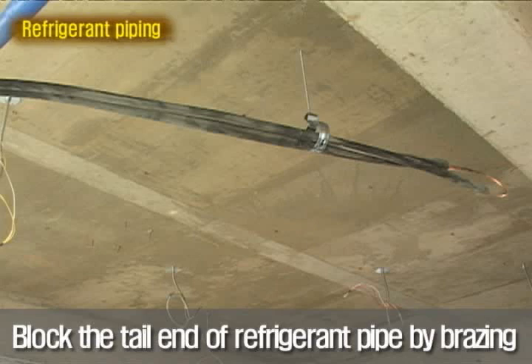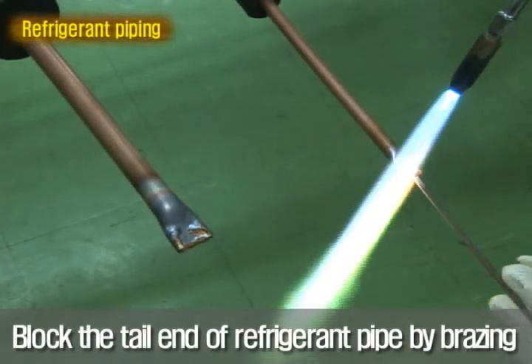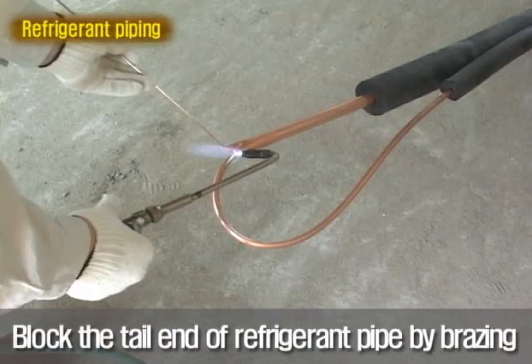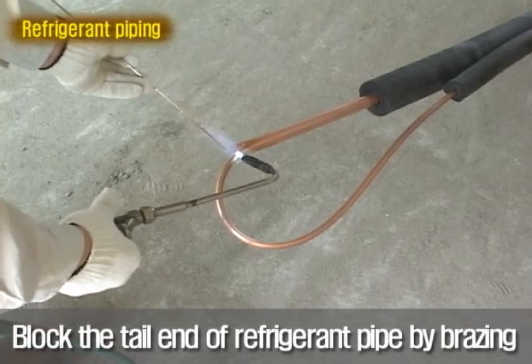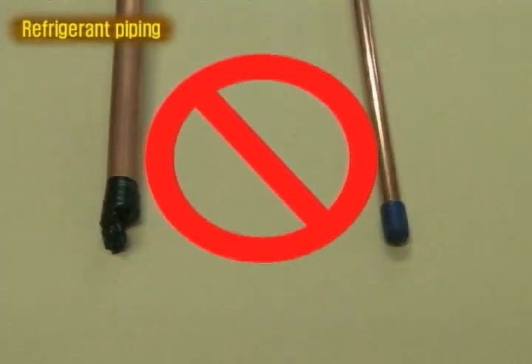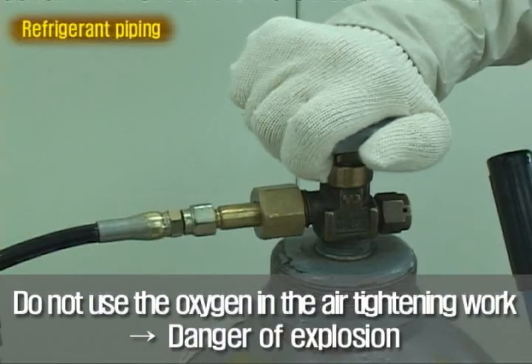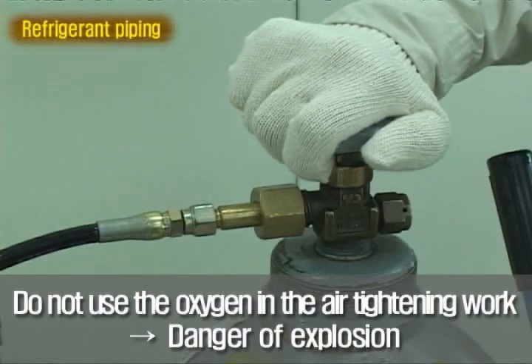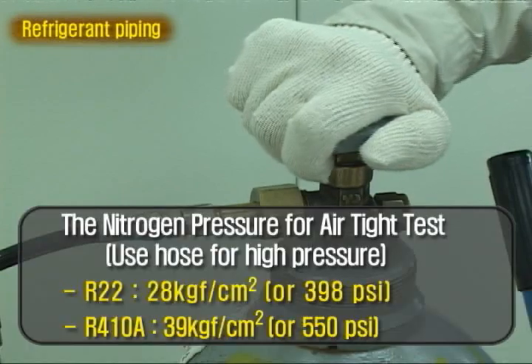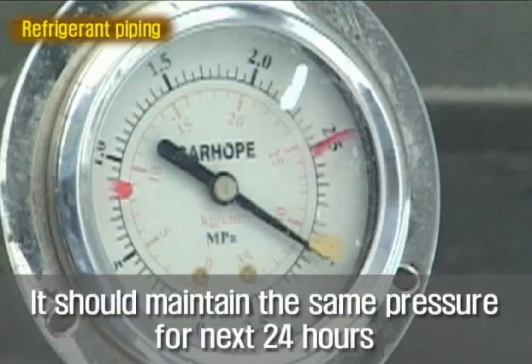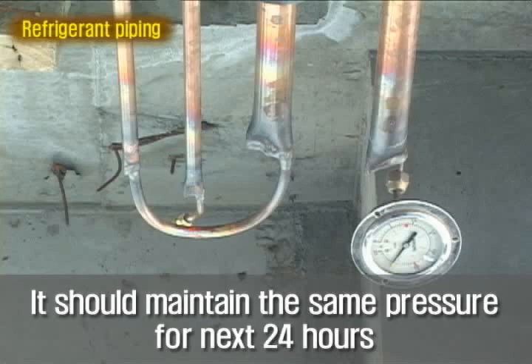After piping work, block the high and low pressure pipe ends by welding to have an airtight test. Do not use caps or insulation tape for that. Connect the ends to a nitrogen pump and charge the gas up to the prescribed value. This pressure should remain high for 1 hour without any loss.